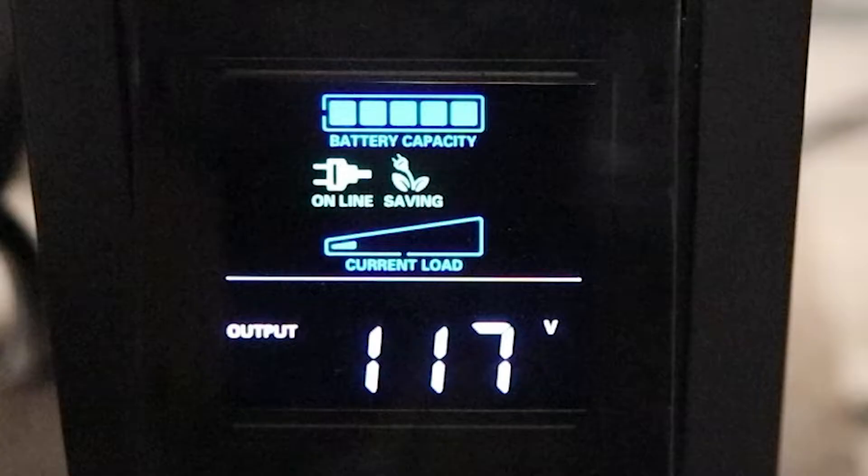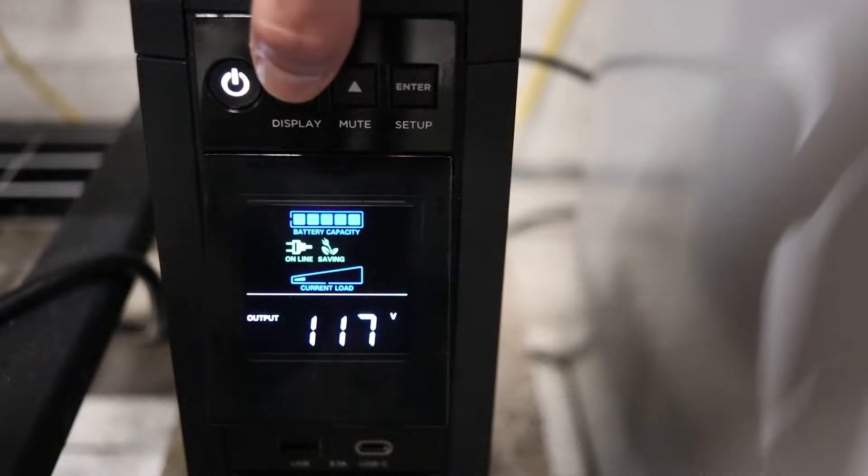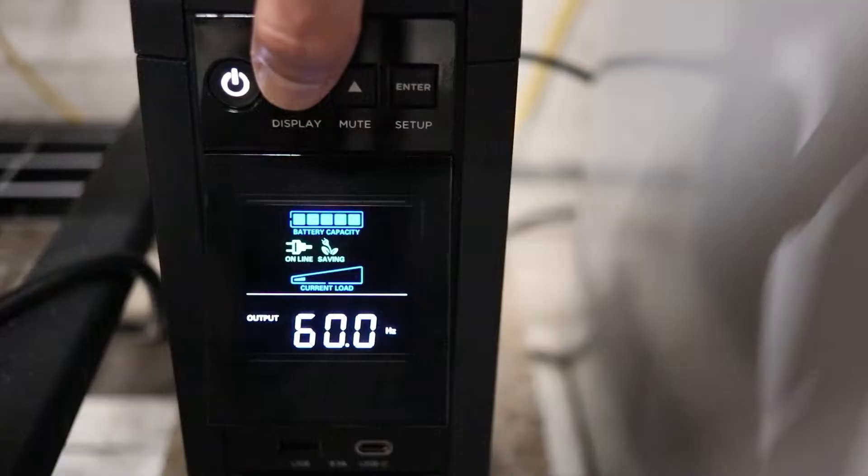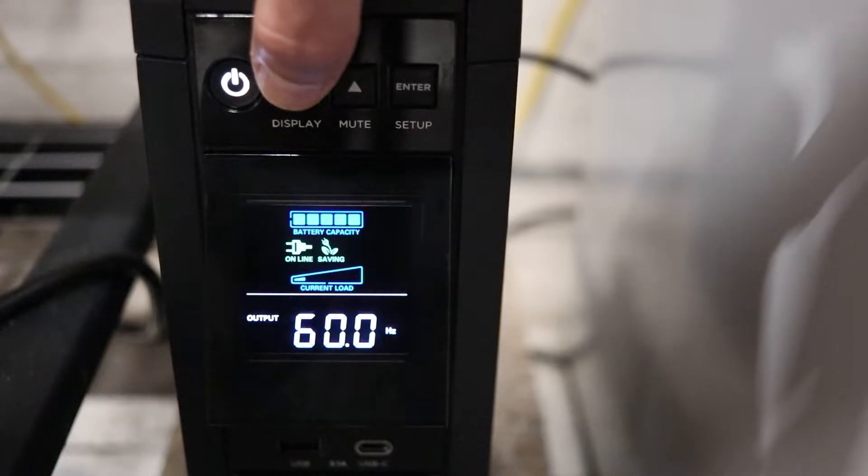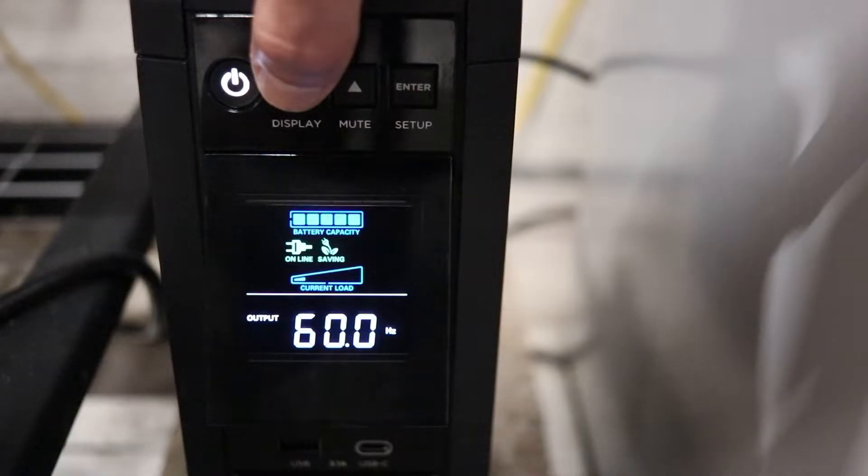And then below that, you'll see the current load, which right now is very low, and then you'll see output of 117 volts, meaning 117 volts is being outputted from this unit. So if we hit the down display arrow, that'll bring you over to hertz, which means this is a pure sine wave, a pure PFC sine wave of 60 hertz.